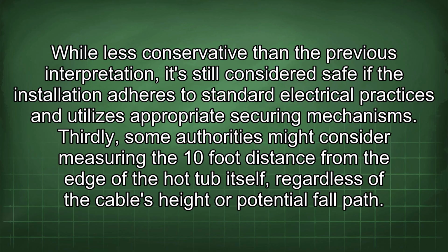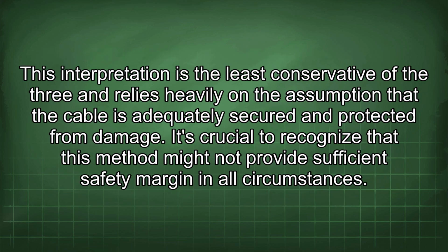Thirdly, some authorities might consider measuring the 10-foot distance from the edge of the hot tub itself, regardless of the cable's height or potential fall path. This interpretation is the least conservative of the three and relies heavily on the assumption that the cable is adequately secured and protected from damage. It's crucial to recognize that this method might not provide sufficient safety margin in all circumstances.